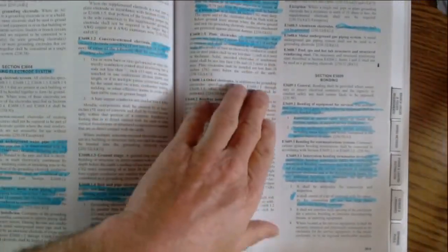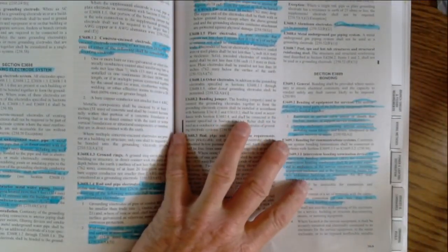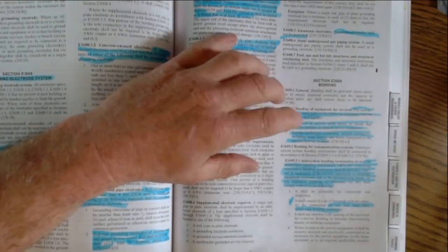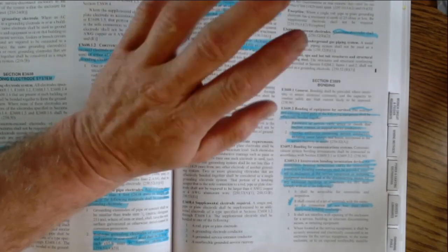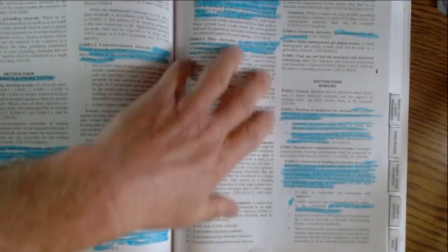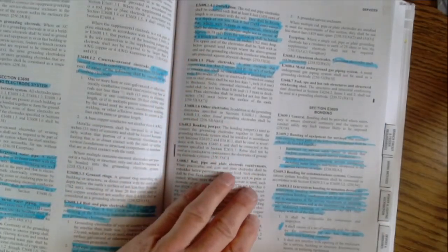Pools. Okay, had a question. Swimming pool bonding. They had the enclosure of the light. They had the stairway in a pool. They had the, what was the other option? Can't remember. And then they had like a towel rack somewhere, a metal towel rack. The answer was the metal towel rack didn't need to be bonded because the other ones were all within a certain distance of the pool or within the pool. So that's how you figure that out.